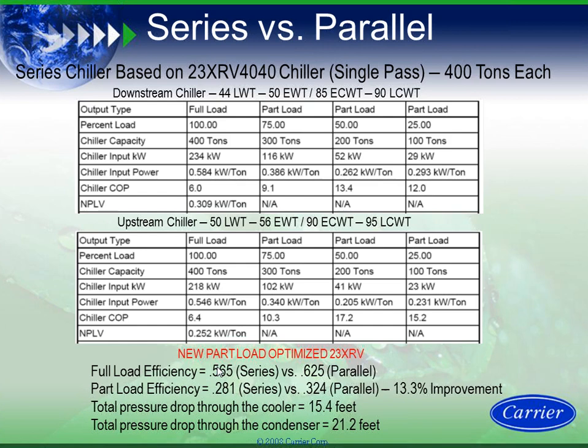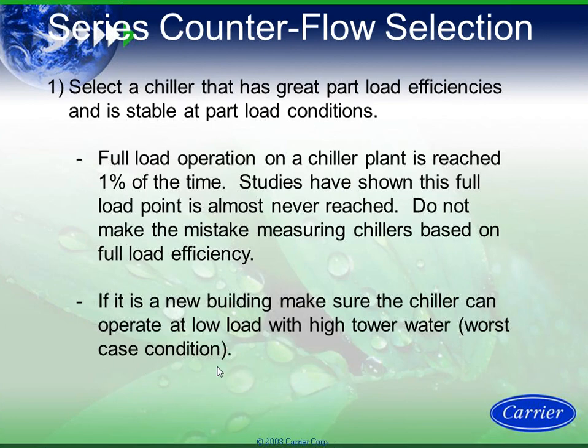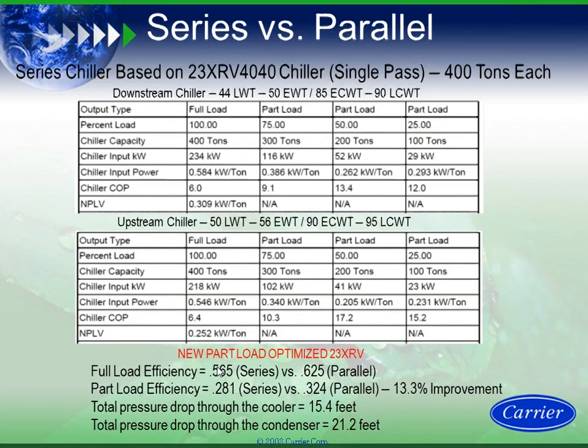my part load value. So with the 23XRV rule of thumb, I could take the same exact machine and go from parallel to series, and without adding a single bit of cost to the chillers, I can gain 10 to 15% efficiency by going from parallel to series on a chiller plant.